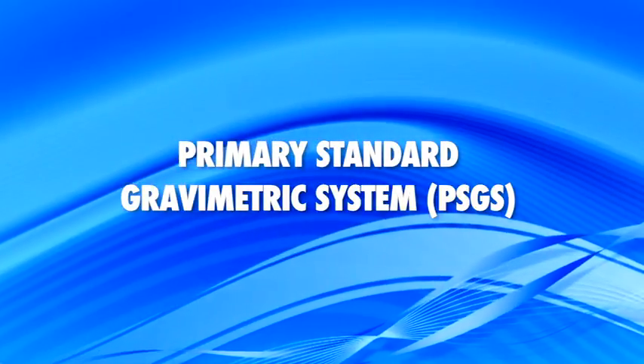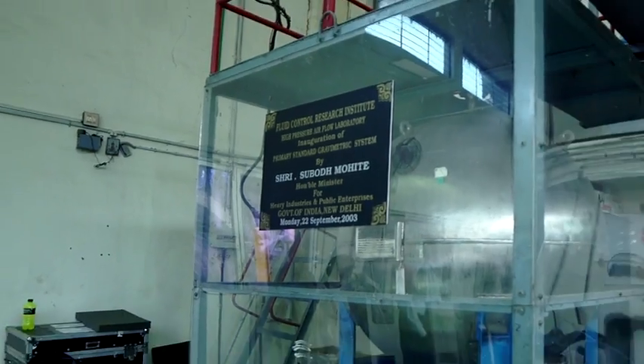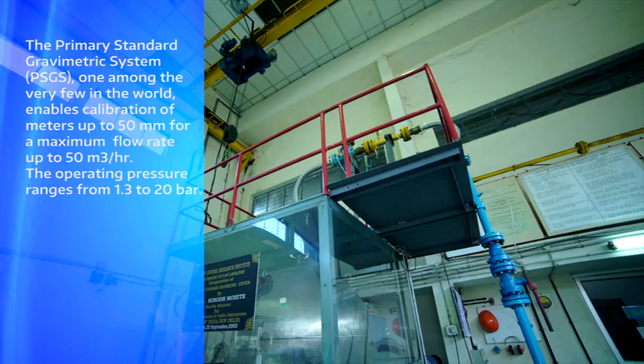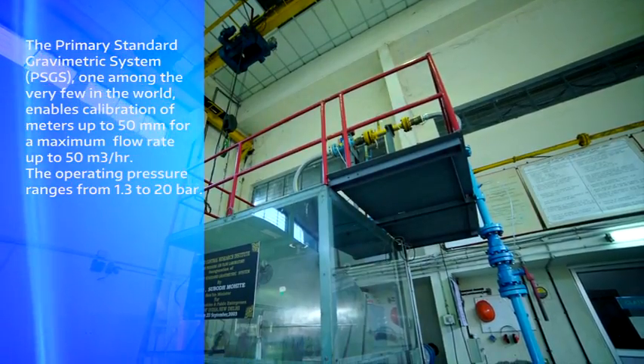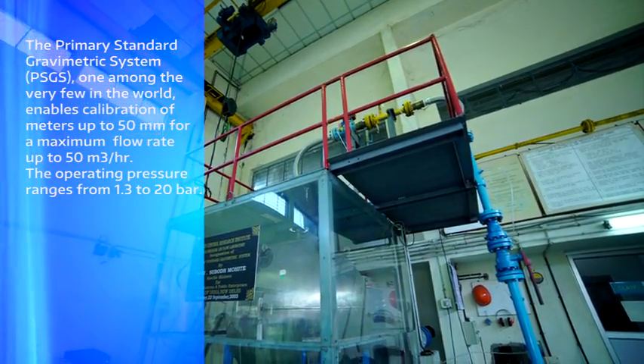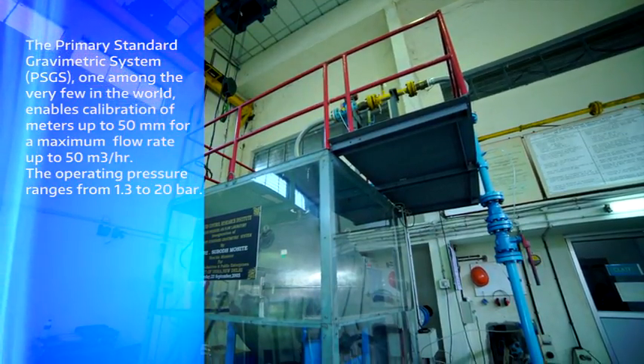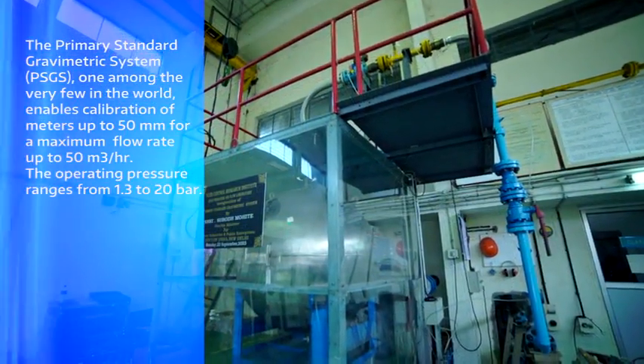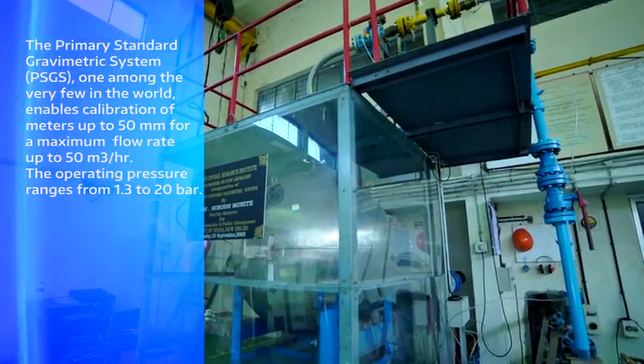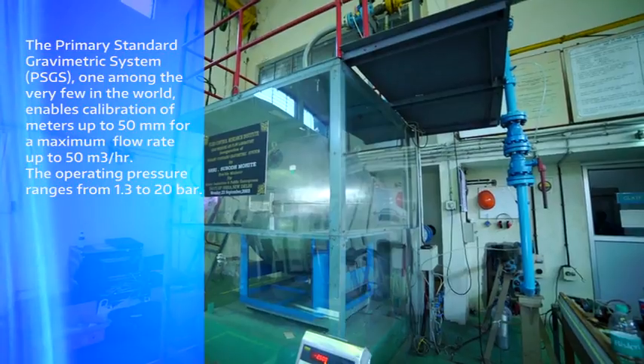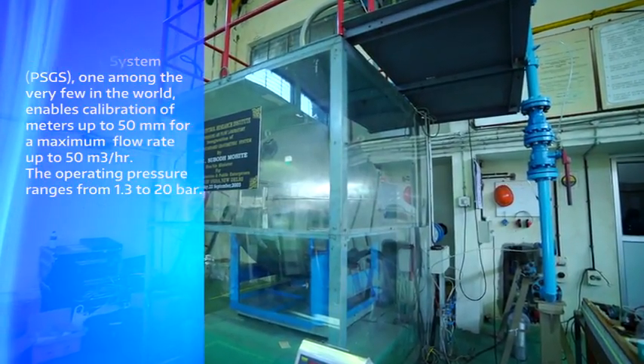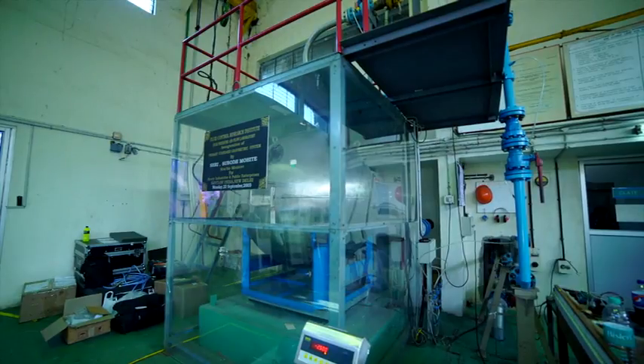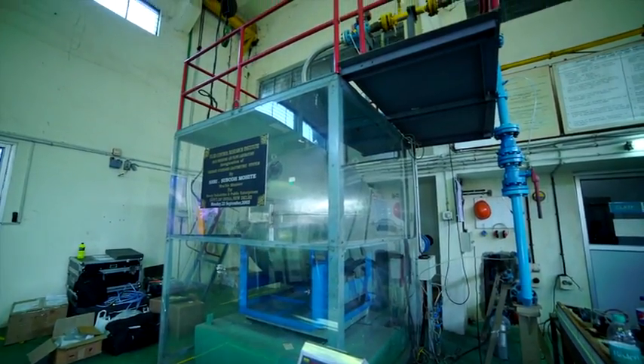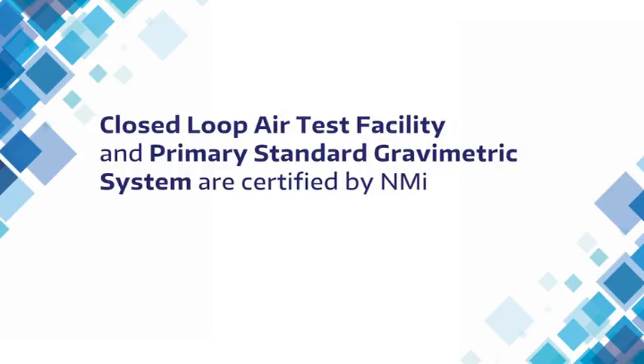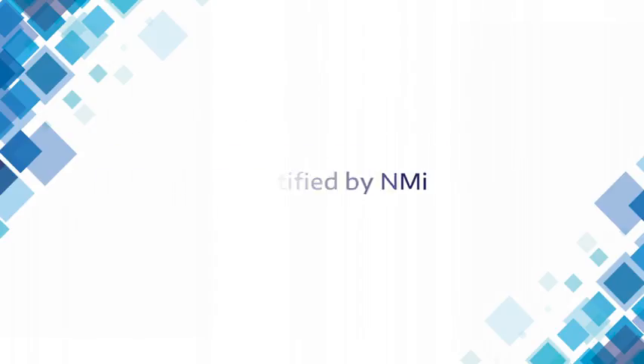The primary standard gravimetric system, one among the very few in the world, enables calibration of air and gas flow meters up to 50 mmNb for a maximum actual volumetric flow rate of 50 cubic meter per hour. The operating pressure ranges from 1.3 to 20 bar. Measurement uncertainties better than 0.1% are achievable, which is among the best in the world. Closed loop air test facility and primary standard gravimetric system are certified by NMI.